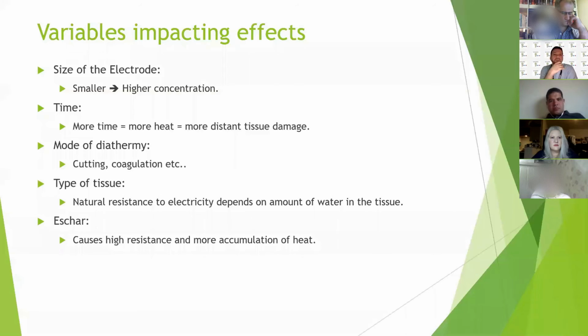What sort of things would affect the function of the coagulation? Number one is the mode you chose. You can choose cutting or coagulation. The more time you apply it, obviously, the more heat that will generate. The size of the electrode: the smaller the size, the more heat it produces. Tissue nature, as we mentioned earlier, especially eschar. Eschar is charred, burned tissue, and it has very high resistance, which means it produces even more heat and more damage.